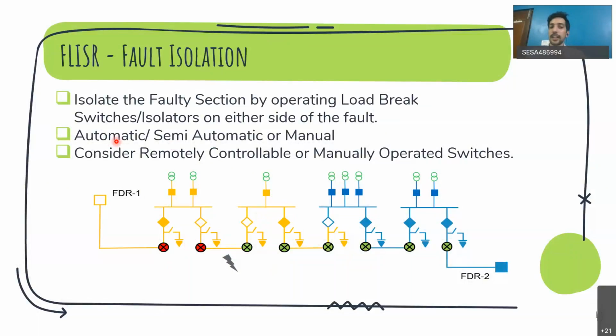Again, this can be automatic, semi-automatic or manual. Automatic means whenever there is a fault, the fault is automatically located and the system automatically performs this. Semi-automatic means when there is a fault, the operator will trigger this application. It will give you the result, saying open this and open this. Then the operator will review it and confirm this is fine, and with one single click he will open both. That is semi-automatic. Manual is, like I told you, where the operator manually sees which FPIs are in set and which are in reset, manually identifies the faulty location and manually isolates it.